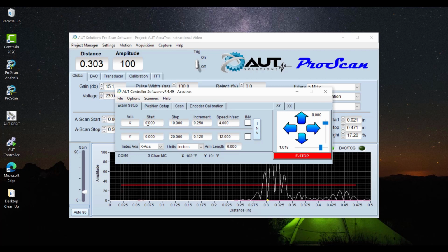So we will currently go through and run through real quick. You'll notice we have our X start and stop. These would be your scan increments. If you're going to run a 100-inch scan, you would simply input 100 into the stop. Now your scanner will run from 0 to 100. However, for this video, we are going to run 10 inches. Same thing with your Y.